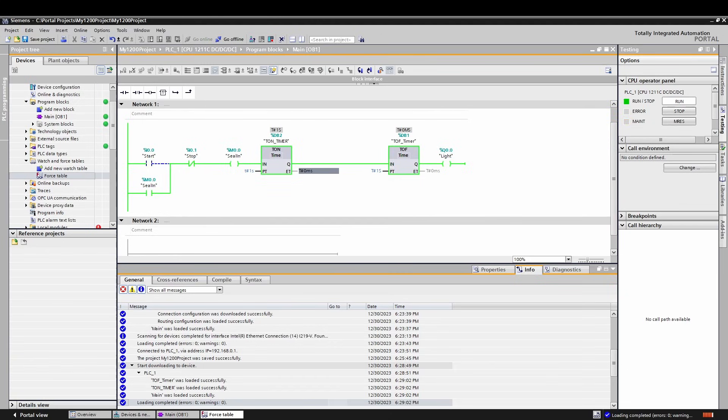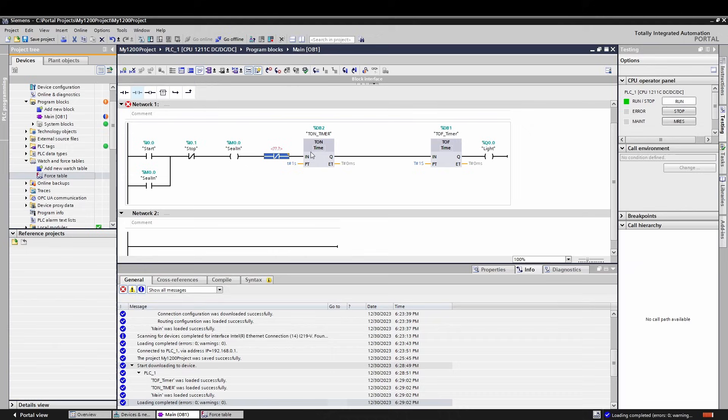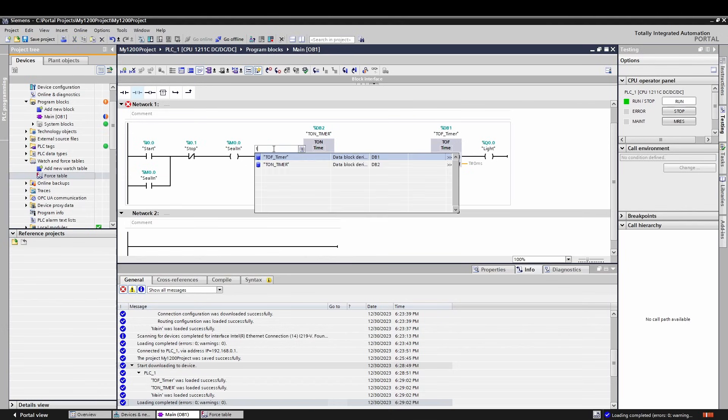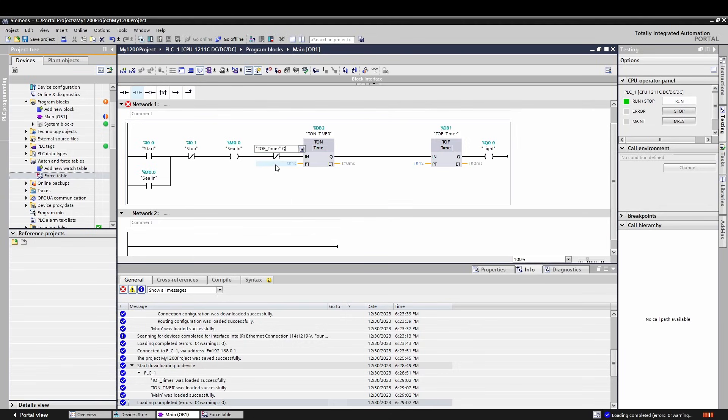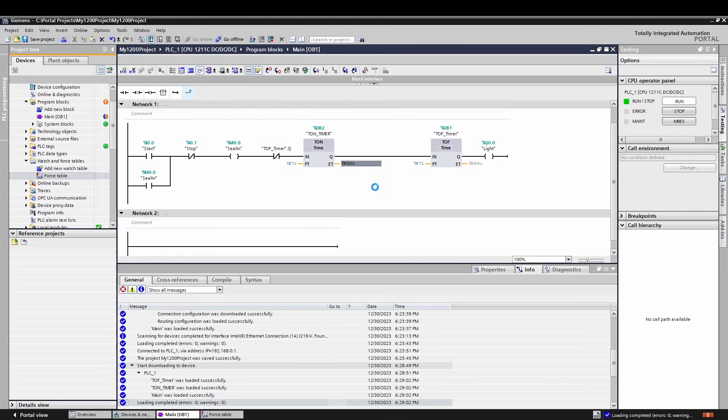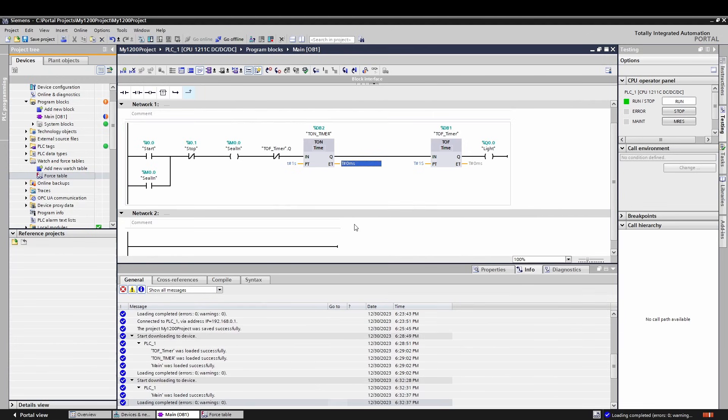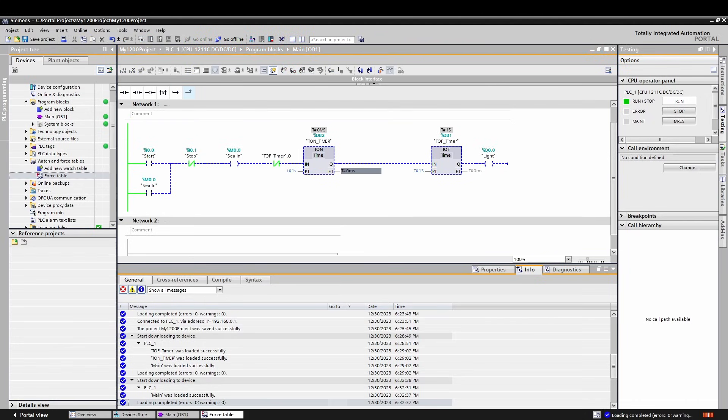Let's add the Q output of this timer into our code. This is where naming your blocks makes a world of difference. Let's add a normally closed contact in front of that TON timer and start typing the name of the TOF block. When it comes up, press Enter and type Q, or select it and press Enter. All right, let's see if this works. Just press Download to download the new code. It immediately comes back online monitoring because our offline and online are now matching. Let's hit stop to reset our logic and press start to test it again. One second delay on, one second delay then off, then repeat.